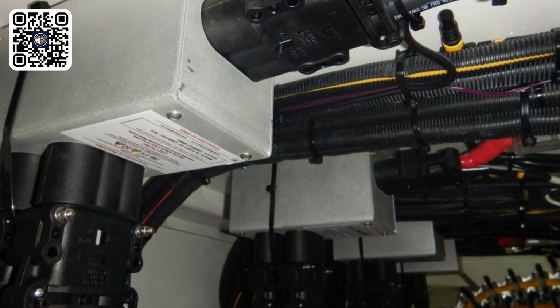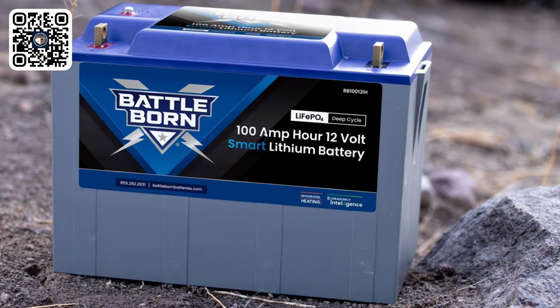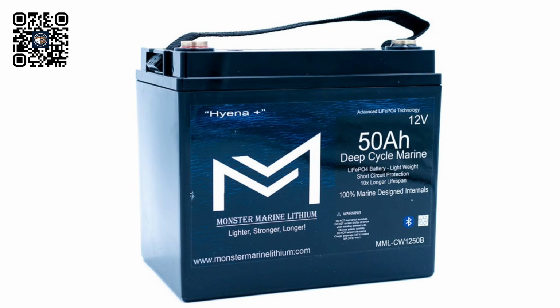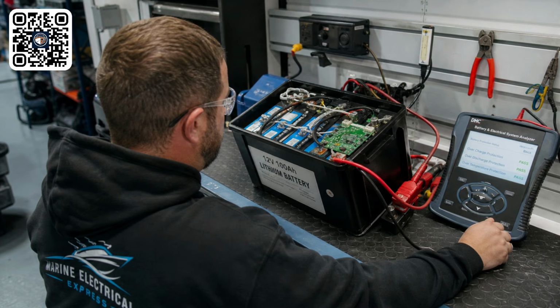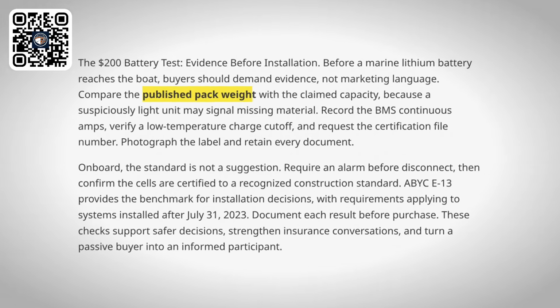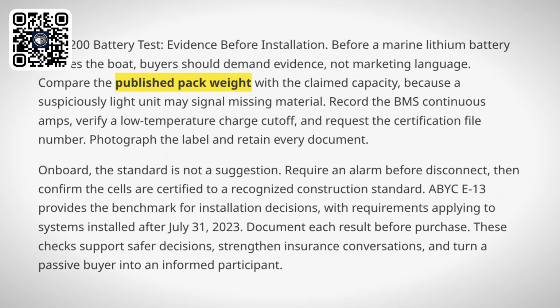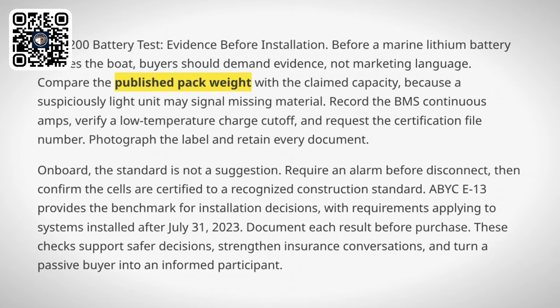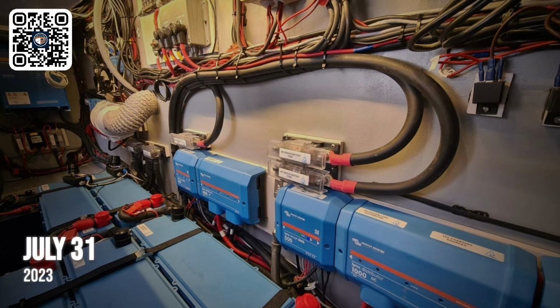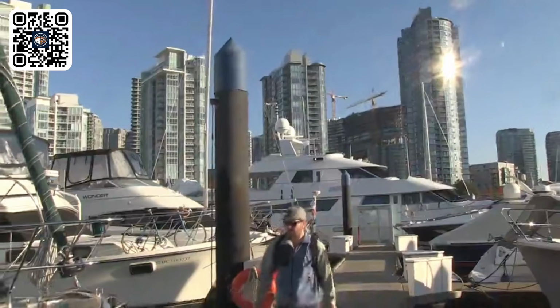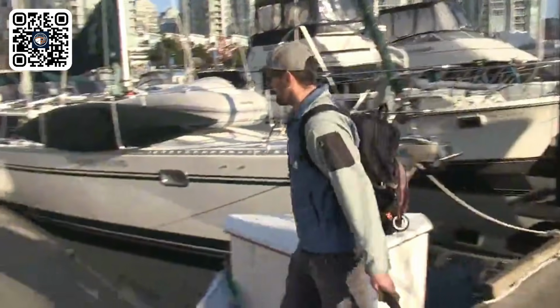On that standard, one last receipt. ABYC E13 covers lithium systems of 600 watt-hours or more, which is about 50 amp-hours at 12 volts, so it covers you. It requires a BMS protecting against overcharge, over-discharge, and over-temperature, recommends an alarm before disconnect, and calls for cells certified to a recognized construction standard. It took effect for systems installed after July 31st of 2023.